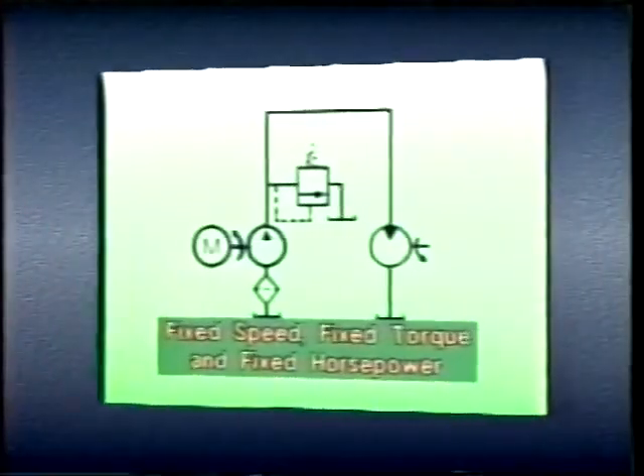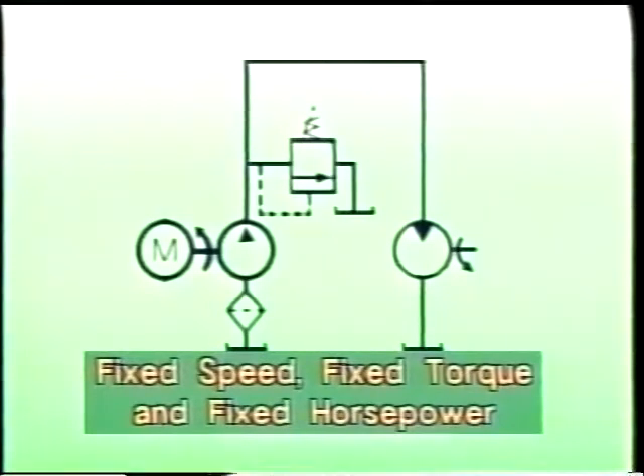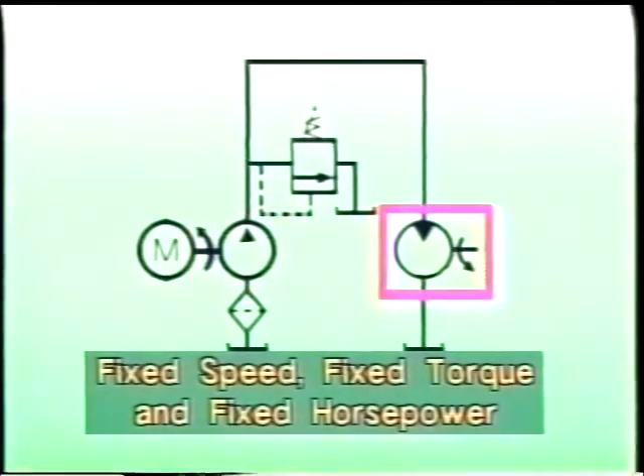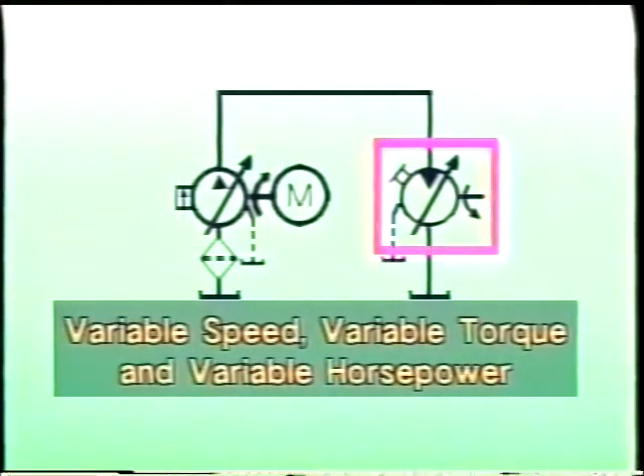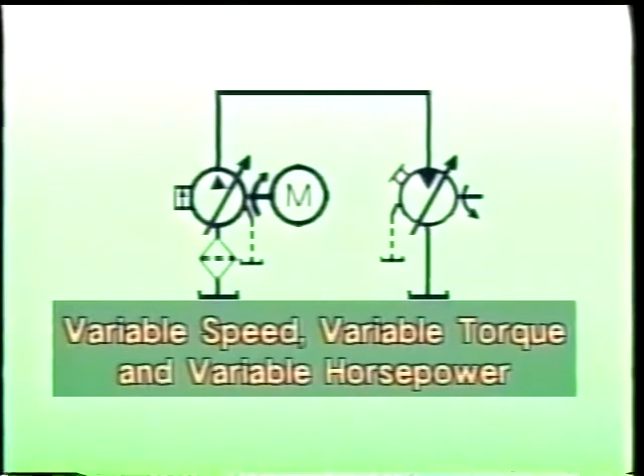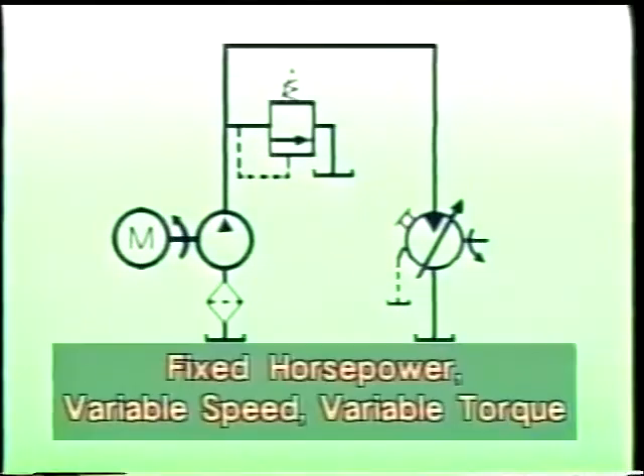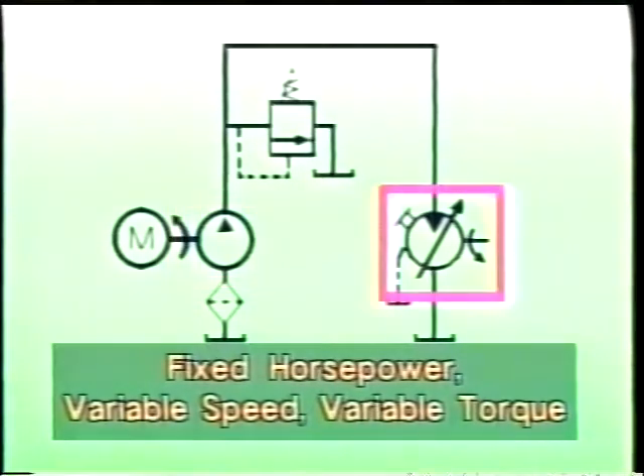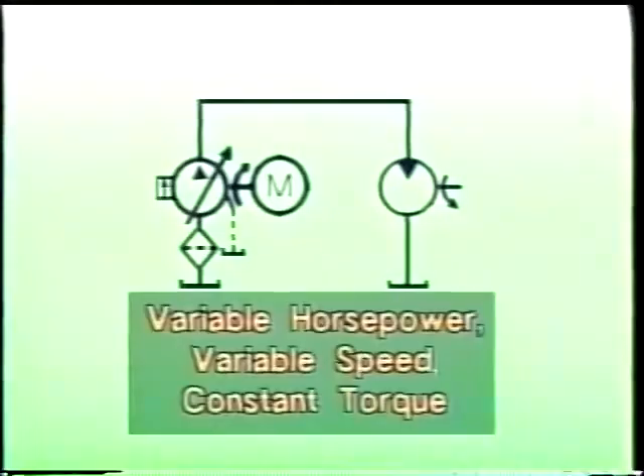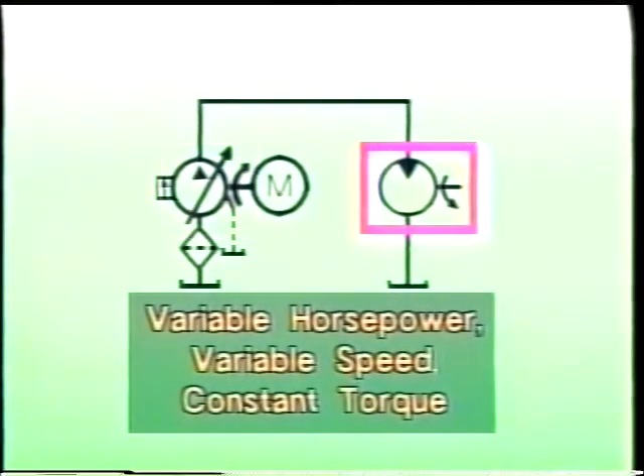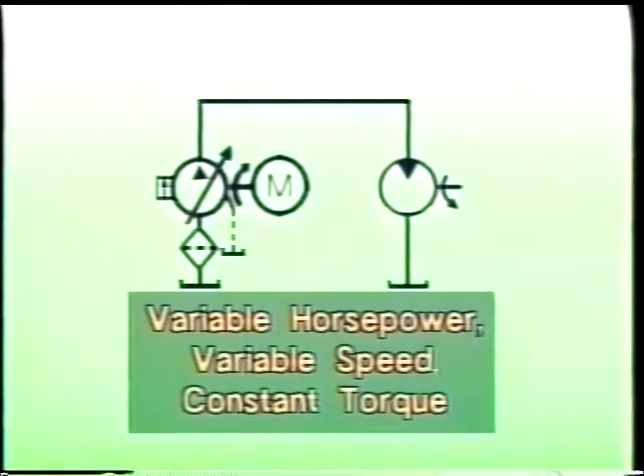The speed, torque, and horsepower of hydrostatic drives and transmissions can be either fixed or variable depending on the type of pump and motor used. If a constant displacement pump and fixed displacement motor are used, the system can deliver only fixed speed, torque, and horsepower. Systems using a variable displacement pump and variable displacement motor provide the most flexibility, producing variable speed, variable torque, and variable horsepower. One common transmission uses a constant displacement pump and a variable displacement motor — horsepower is fixed but speed and torque can be varied. Another uses a variable displacement pump and a fixed displacement motor, producing variable horsepower, variable speed, and constant torque.